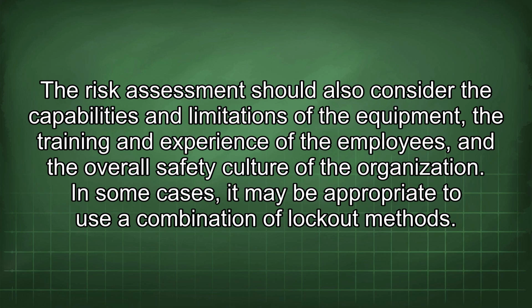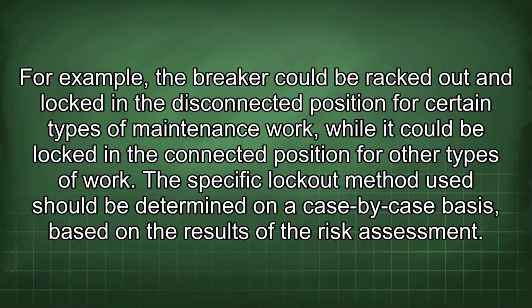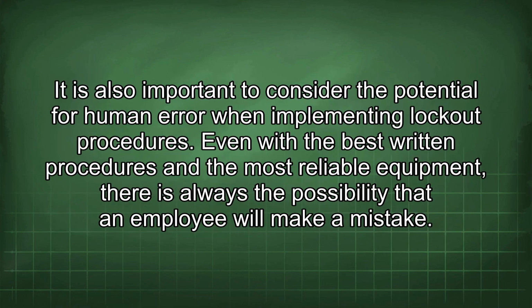In some cases, it may be appropriate to use a combination of lockout methods. For example, the breaker could be racked out and locked in the disconnected position for certain types of maintenance work, while it could be locked in the connected position for other types of work. The specific lockout method used should be determined on a case-by-case basis, based on the results of the risk assessment. It is also important to consider the potential for human error when implementing lockout procedures.